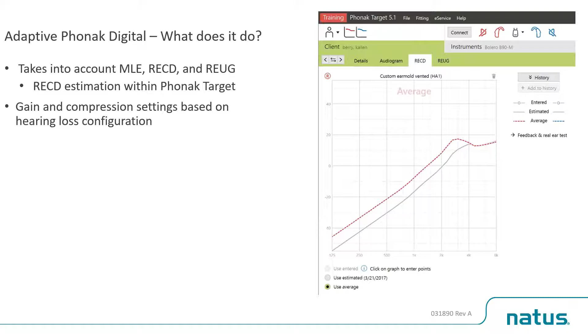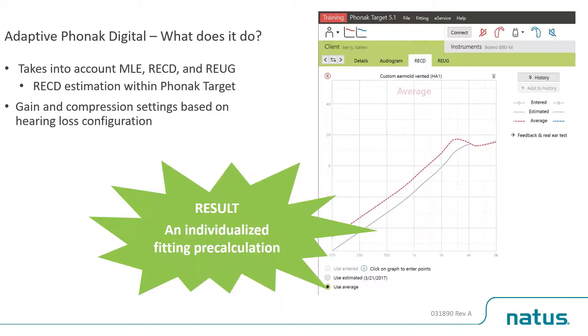So Adaptive Phonak Digital, what is it? What does it do? It takes into account the microphone location effect, the real ear to coupler difference, and the real ear unaided gain. So it's an estimated RECD within Phonak Target. The gain and compression settings are based on the hearing loss configuration. So that result really guides you to an individualized fitting pre-calculation. So it will have an estimate without taking any of these assumptions into account, and then give you a more individualized target.